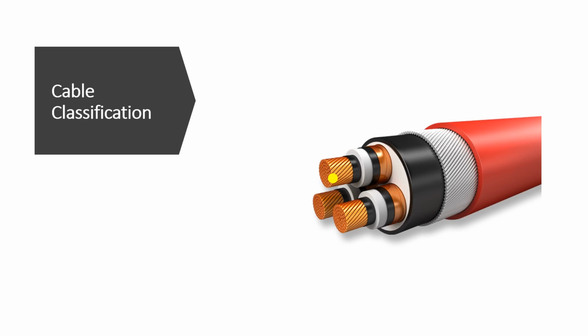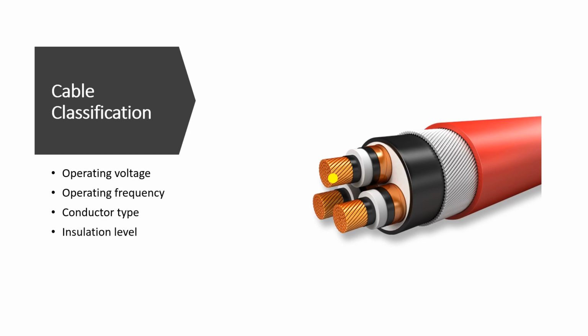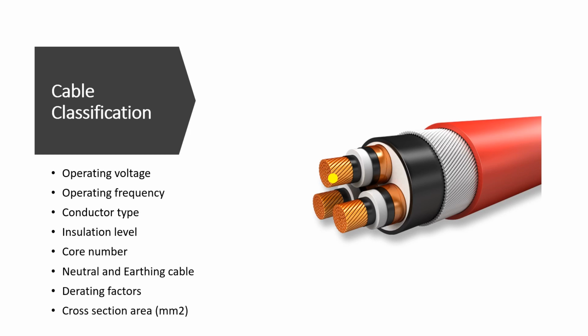The first factor is the operating voltage of the cable. The second factor is the operating frequency of the cable. The third one is the type of the conductor used inside the cable, also the insulation level of the cable, the number of cores inside a cable, the neutral and earthing cable, and the derating factors. And finally, the cross-sectional area of the cable.